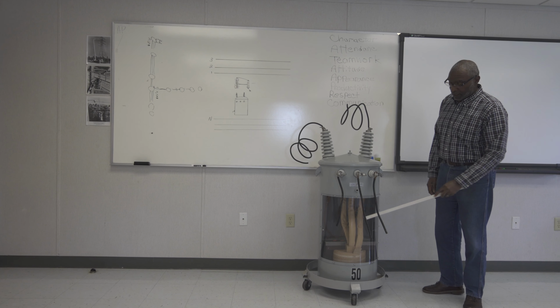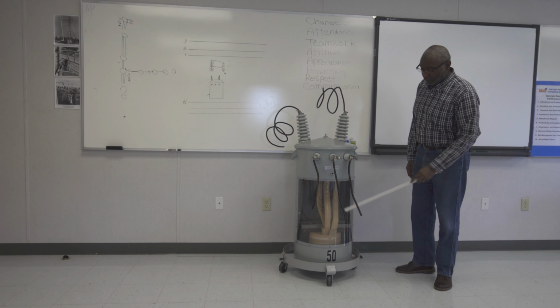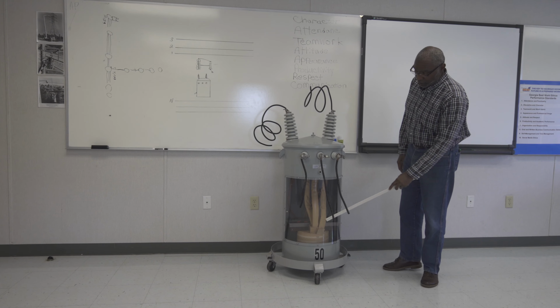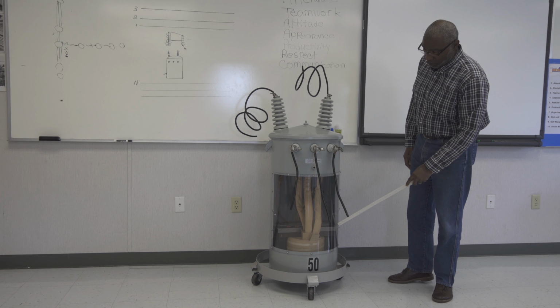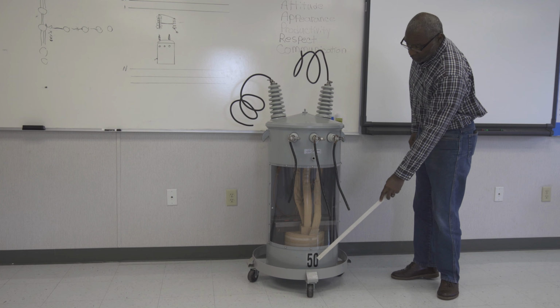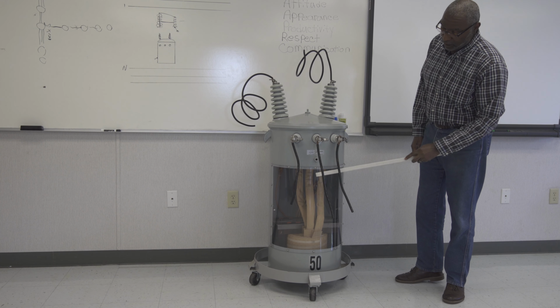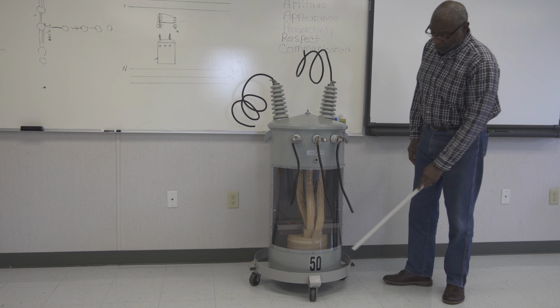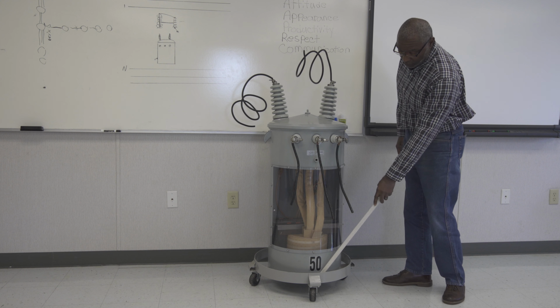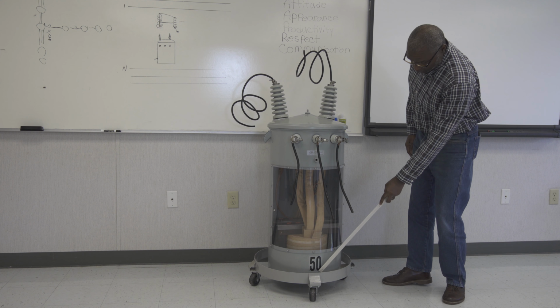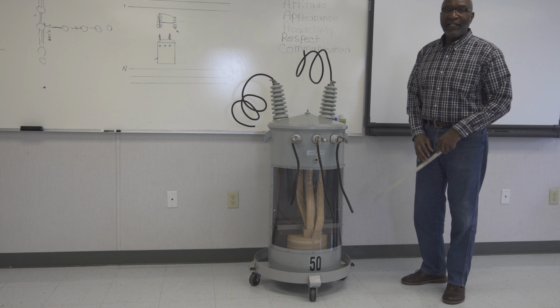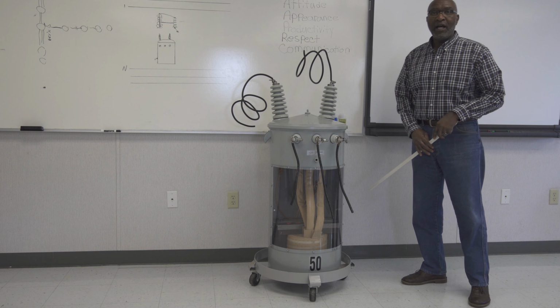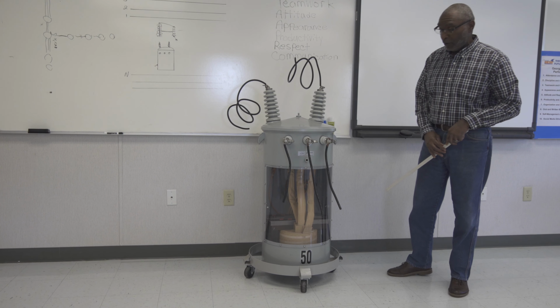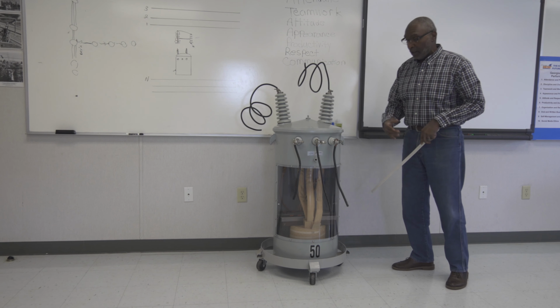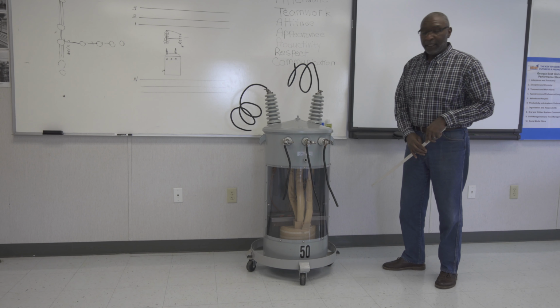Typically, because this is a display with the plexiglass showing the windings of the transformer insides, this number will usually be up around here somewhere. Also down here, you can't see another sticker that's indicating that this transformer is a non-PCB, which is very important to know, and we've talked about that already.